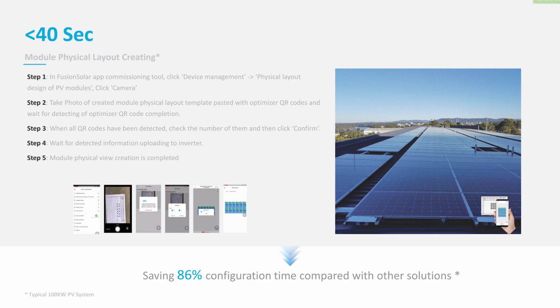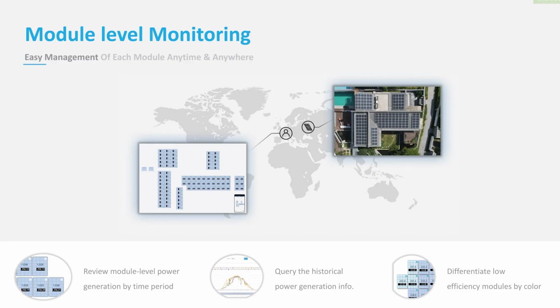Basically, with the optimizers, you can dial down to every panel. You can see the voltage and the current for every panel, and if you run a report, you can see if there's a PV module that's not performing, based on the rest of them. Module level monitoring, this is what I just explained. You can monitor each PV module individually. That helps to identify any modules that are not working properly, have micro cracks, have diode problems, have a cracked panel, or have hot spots.